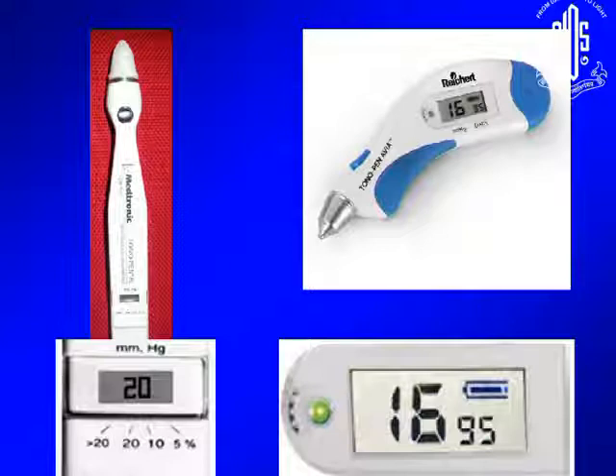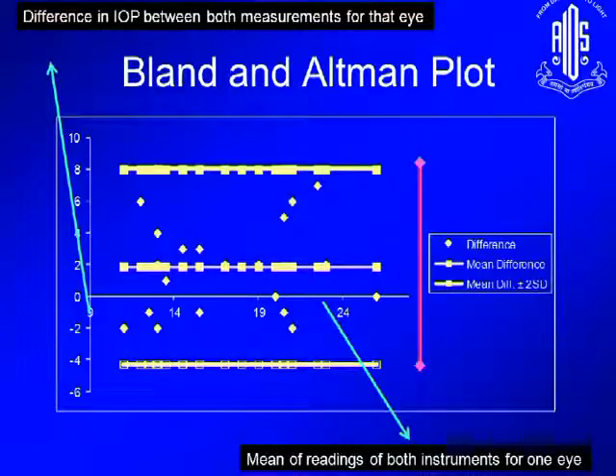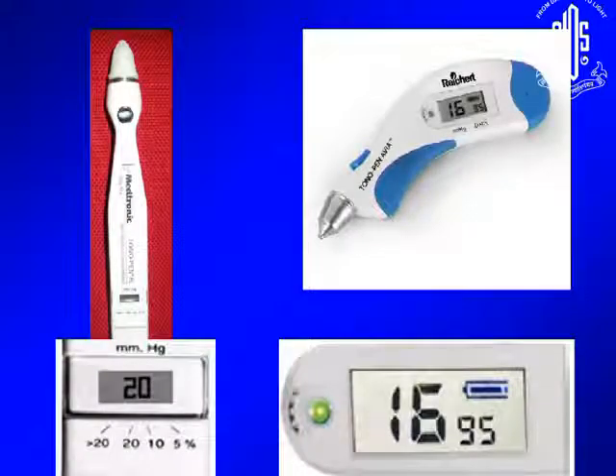Again, with the Tono-Pen, it's very often recommended that you take a mean of 3 readings in order to get what you want. With the Avia, it gives the intraocular pressure the same way, but it gives you the actual figures of 95% confidence instead of just the 5%. The other advantage of the Avia is that the screen that you see is there on both sides. So you don't need to bend your head to look at it. You can look at it either way, use left-handed or right-handed.